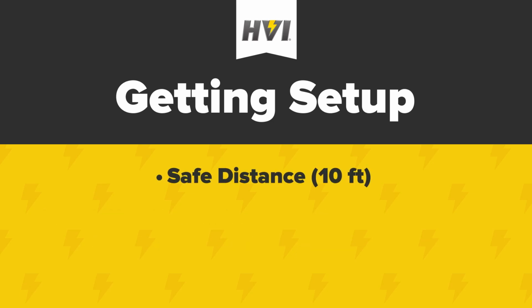Move the ALT series Hipot to a location that allows for an easy view of display meters and a safe distance away from the DUT. We recommend that the control unit is placed at least 10 feet away from the DUT, as well as the separate high-voltage section, which should be removed entirely from the hand truck and placed away from both the DUT and the control unit. Make sure you are wearing personal protection equipment, or PPE.